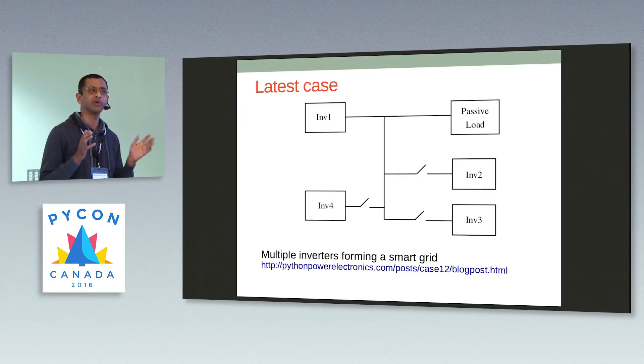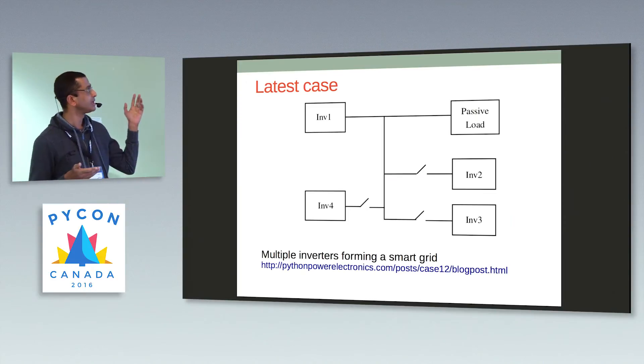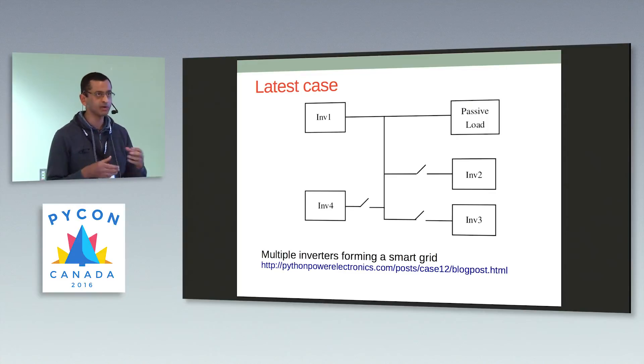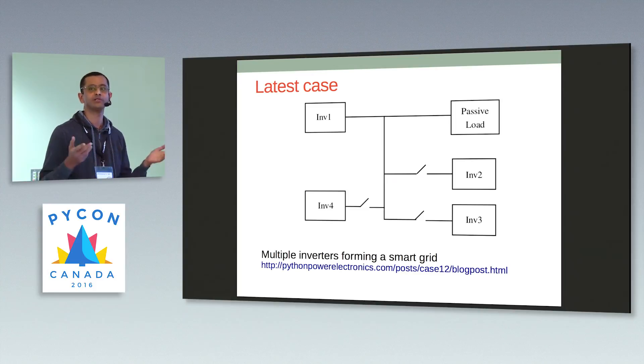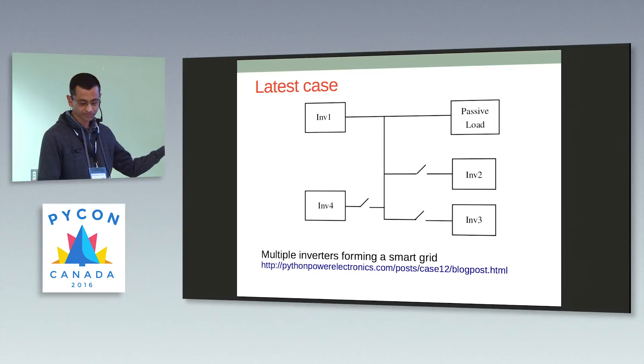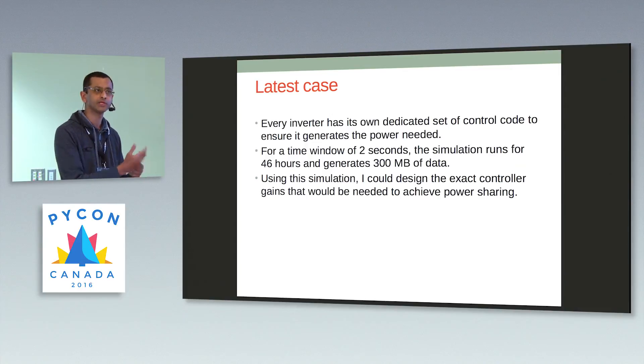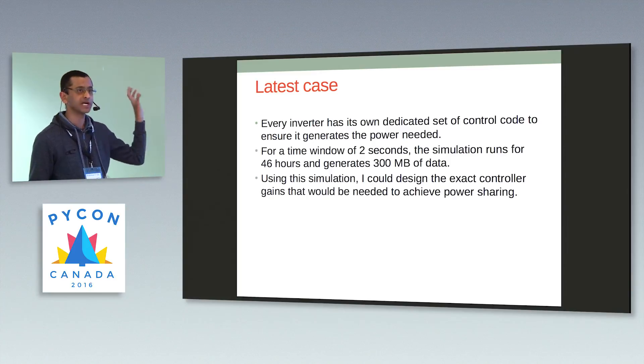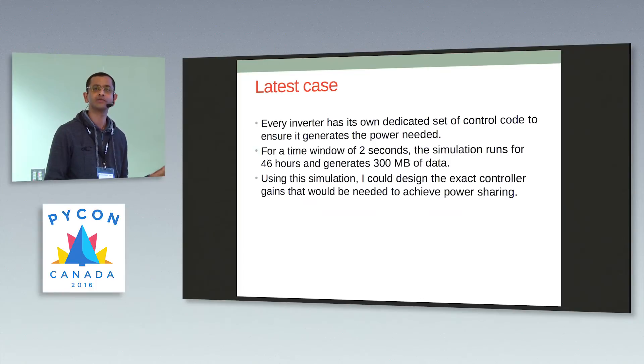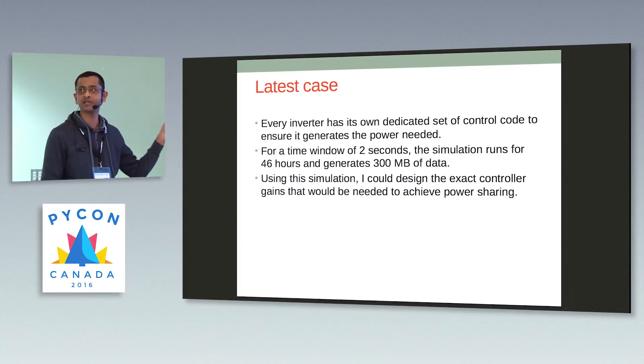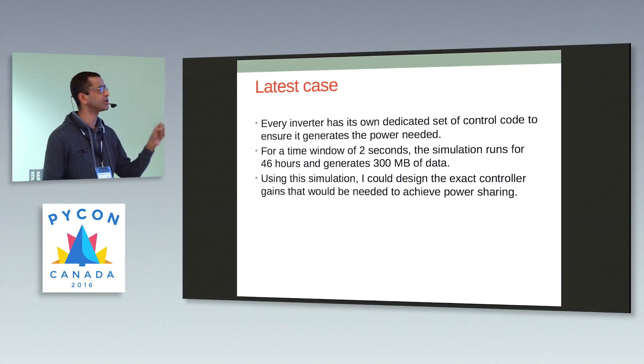To give you one example of what I can do with the circuit simulator: this is what is called a smart grid. A smart grid means you have multiple inverters connected together to form a system. These multiple inverters can be renewable energy sources — solar, wind — they can have storage devices like batteries, and finally you have loads. This runs for a time window of two seconds at a simulation time step of 100 nanoseconds, runs for 46 hours, and generates 300 megabytes of data. Using this simulation, I'm able to tune the control parameters to achieve power sharing.